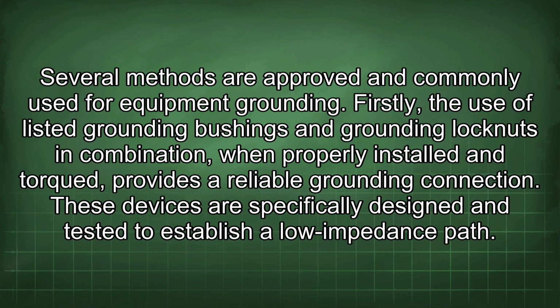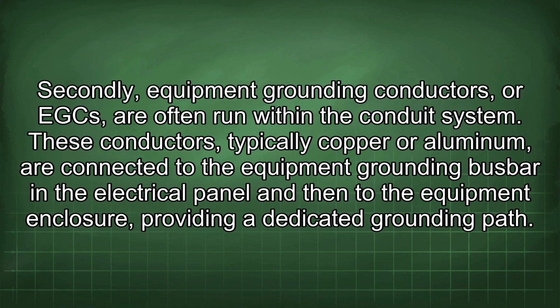Firstly, the use of listed grounding bushings and grounding locknuts in combination, when properly installed and torqued, provides a reliable grounding connection. These devices are specifically designed and tested to establish a low impedance path. Secondly, equipment grounding conductors, or EGCs, are often run within the conduit system. These conductors, typically copper or aluminum, are connected to the equipment grounding busbar in the electrical panel and then to the equipment enclosure, providing a dedicated grounding path.